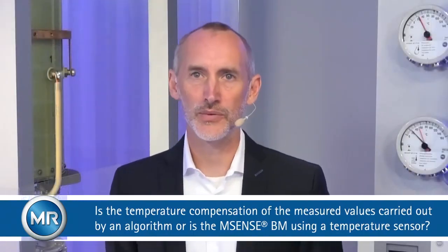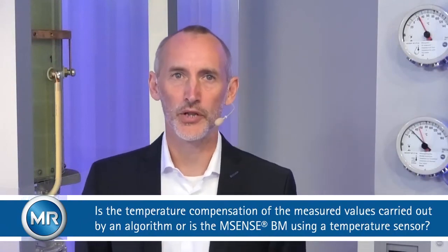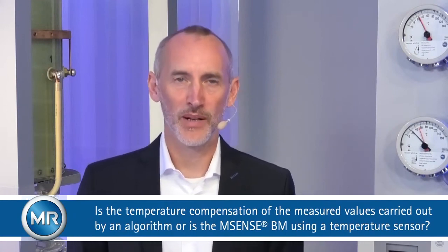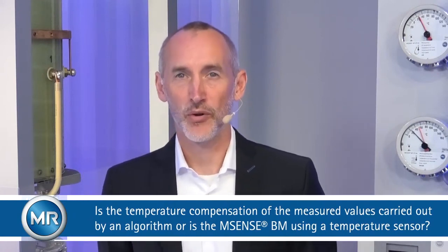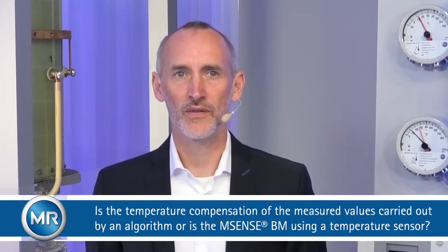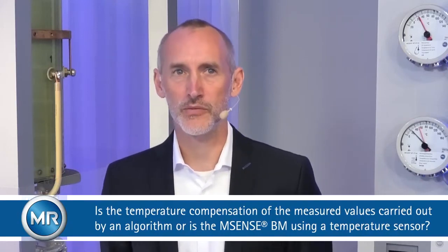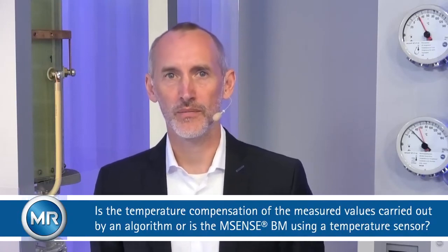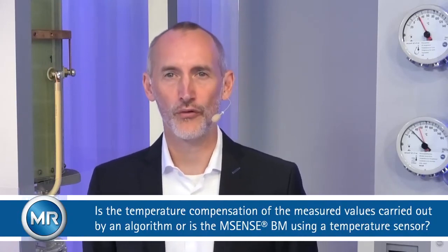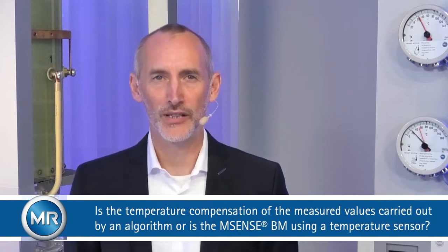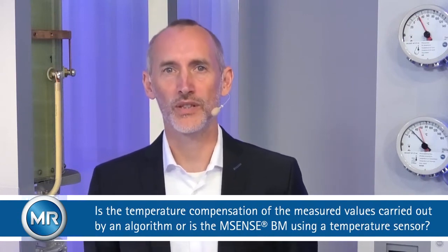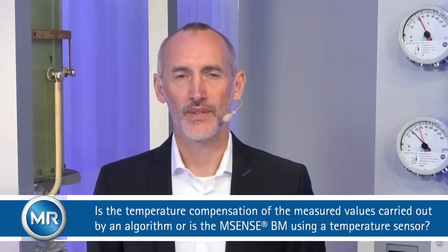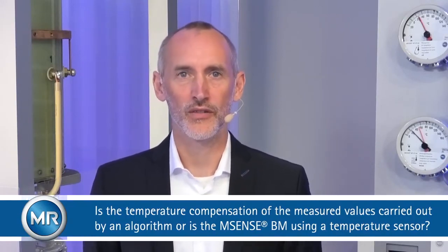We have an algorithm that is taking care of the temperature impact on the bushings. That was earlier explained today, and that's one of the benefits, that we have the possibility to compare 3 bushings at the same time. So we do not need a mathematical correction of the measured values. We can straightforward use the data we are getting from our algorithm, and that's a certain benefit of this system here.